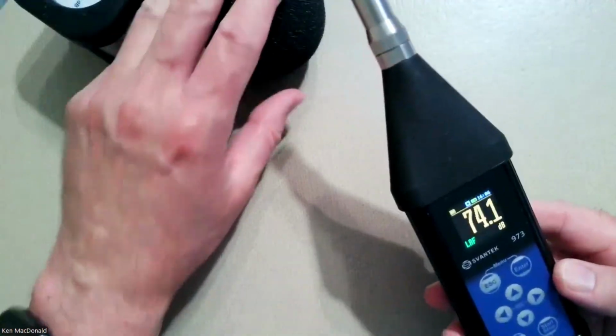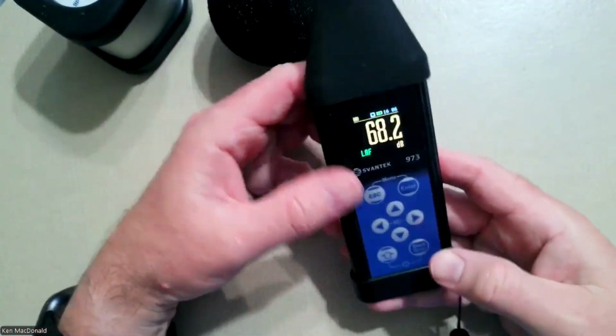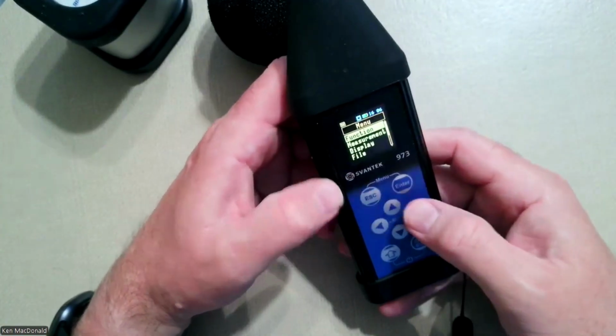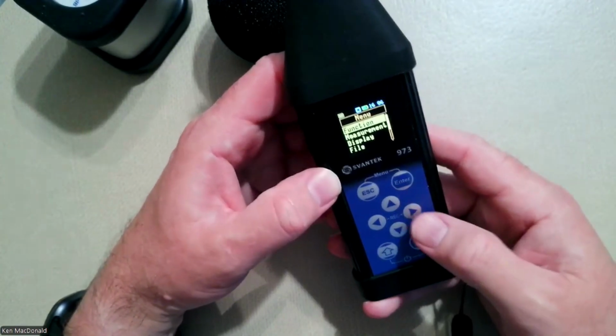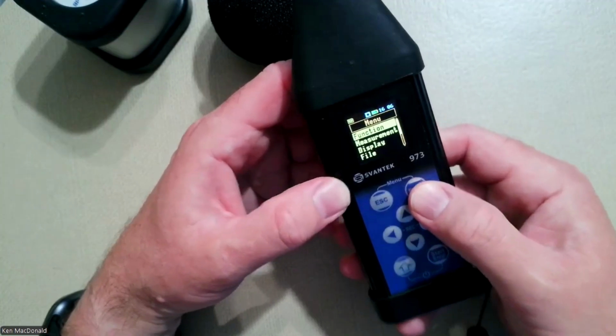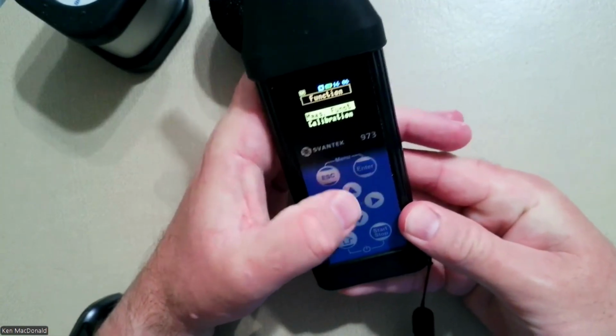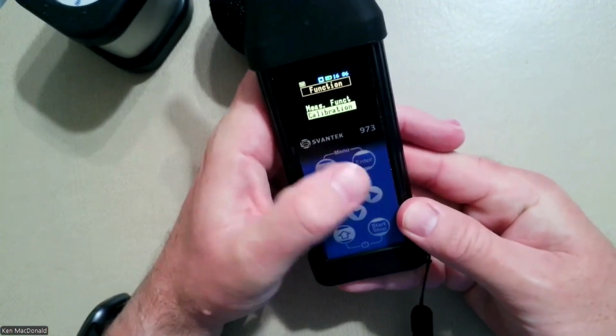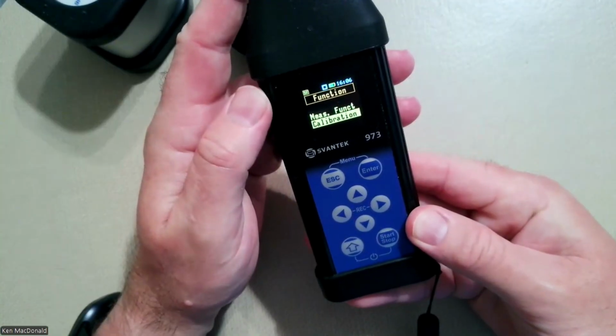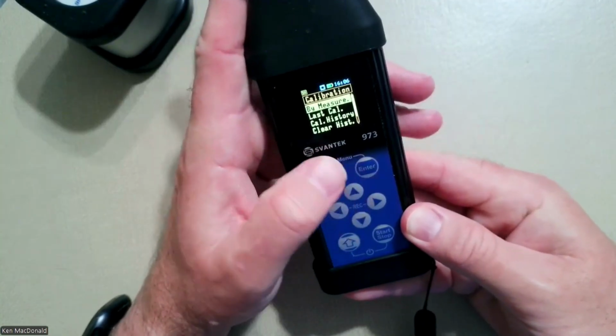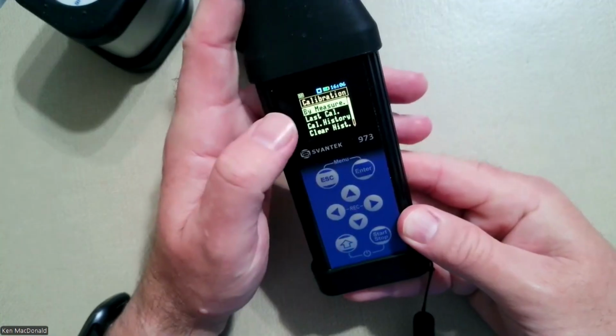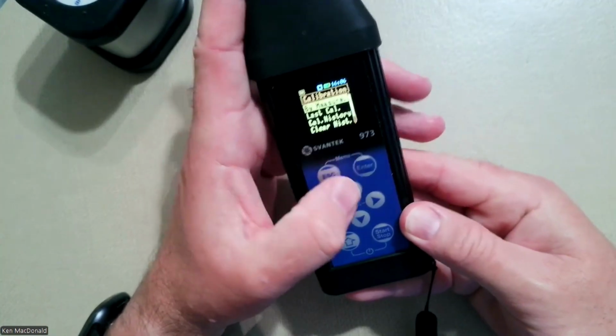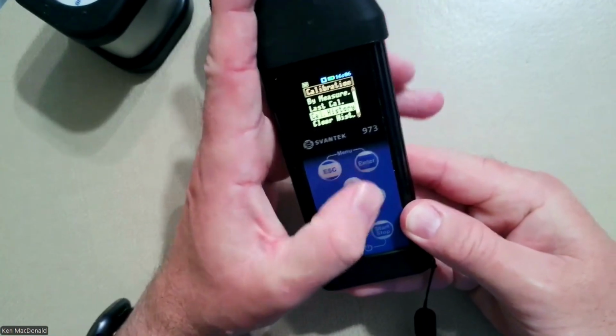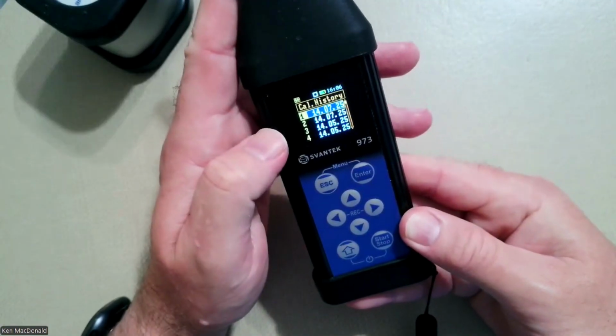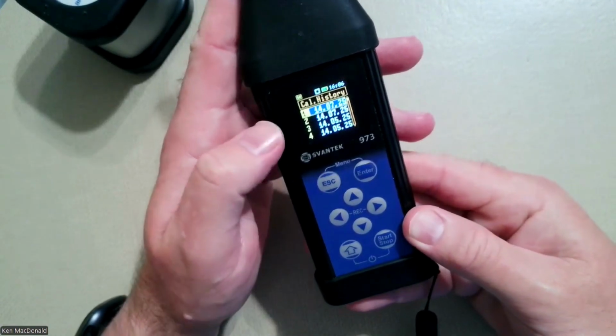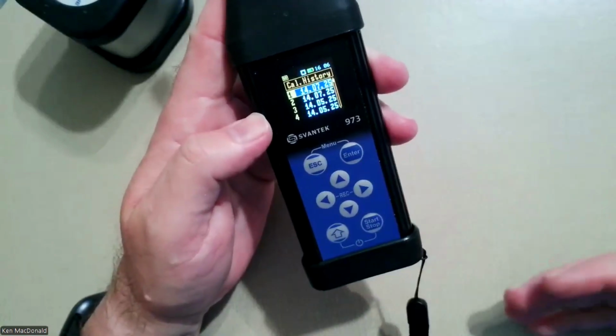So anyway, getting into this a bit more now, if I go into the menu, I can go through and look under function. If I go into calibration, I used the automatic calibration that I showed you. If I went into calibration this way, I could do the same calibration here by measurement. I can also look at the calibration history here and go through each one of the recorded histories. So that's really the basics of the calibration.